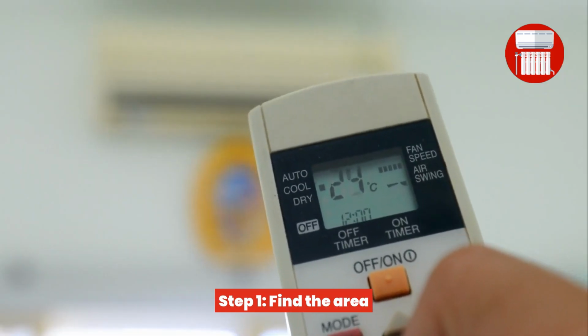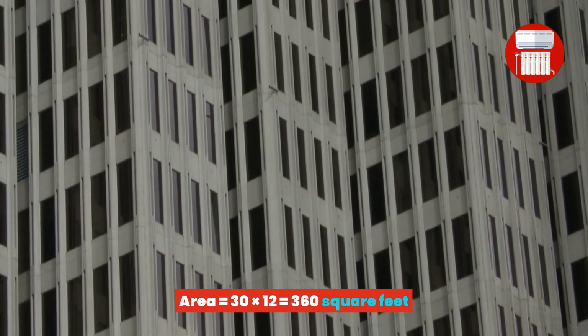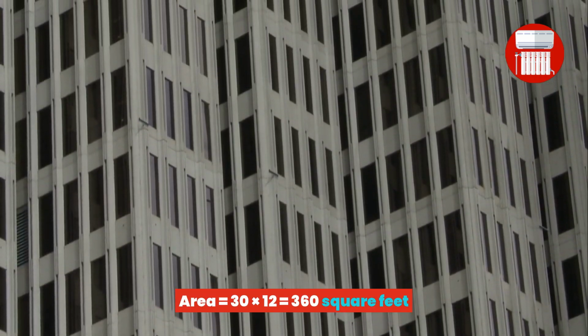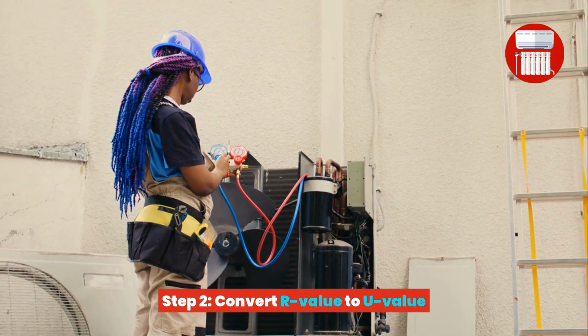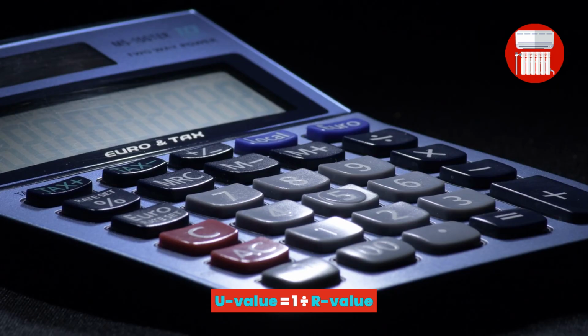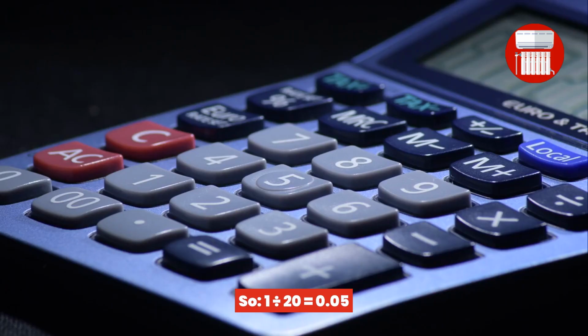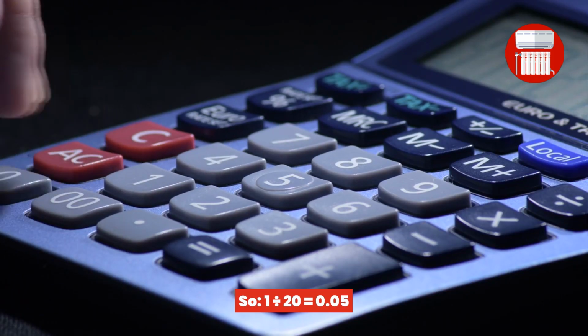Step 1. Find the area equals 30 times 12 equals 360 square feet. Step 2. Convert R value to U value. U value equals 1 divided by R value, so 1 divided by 20 equals 0.05.